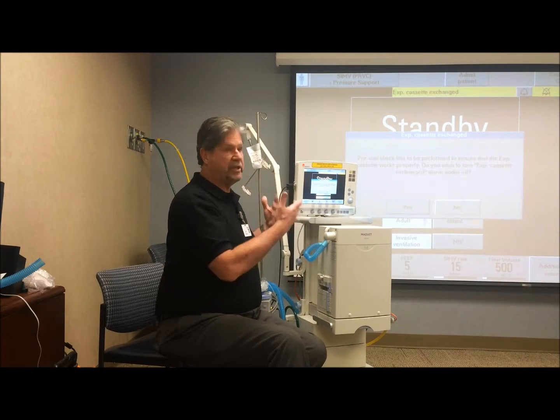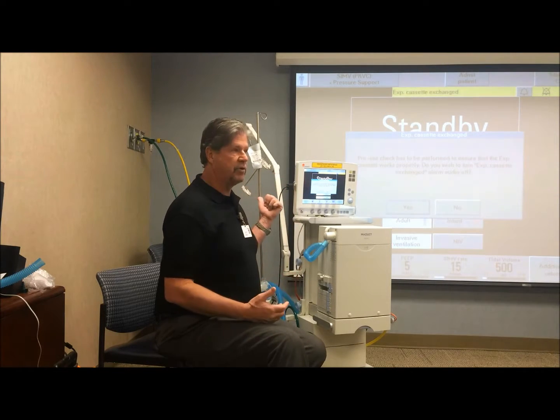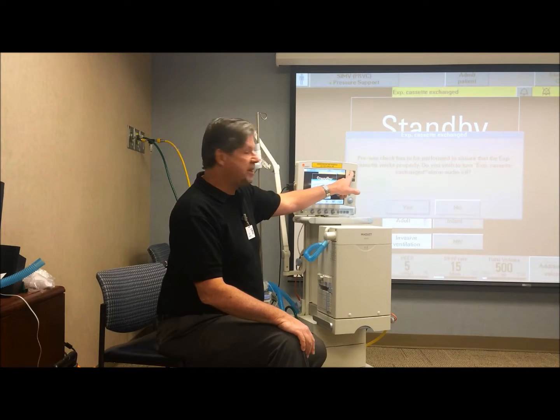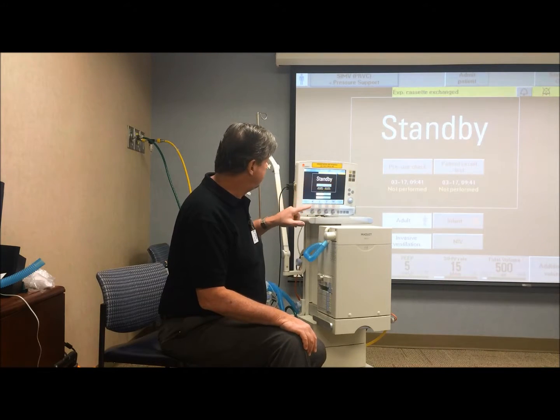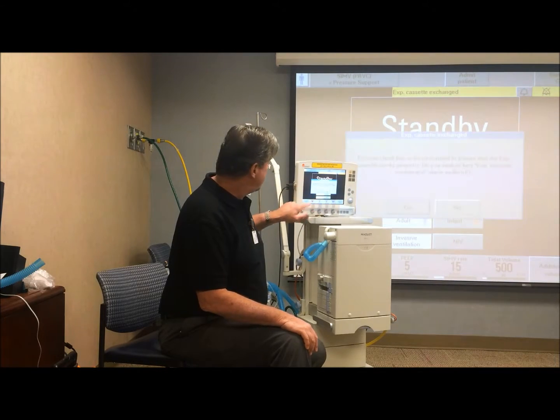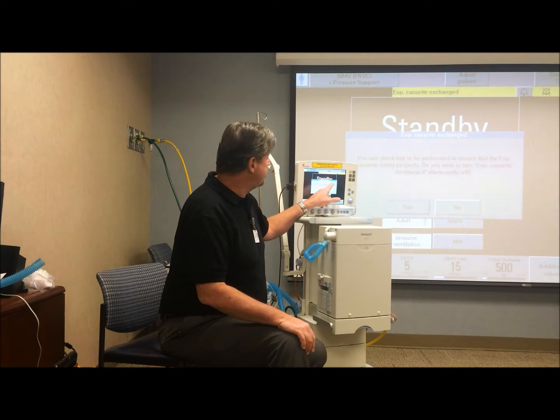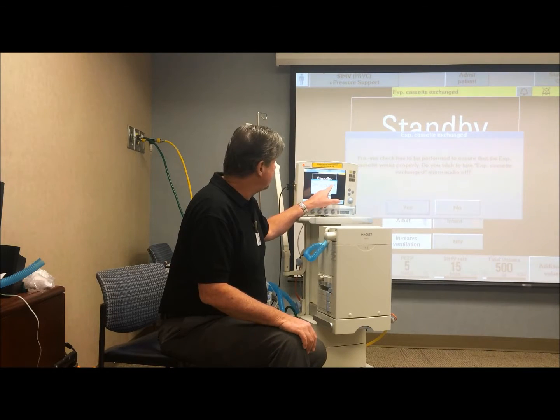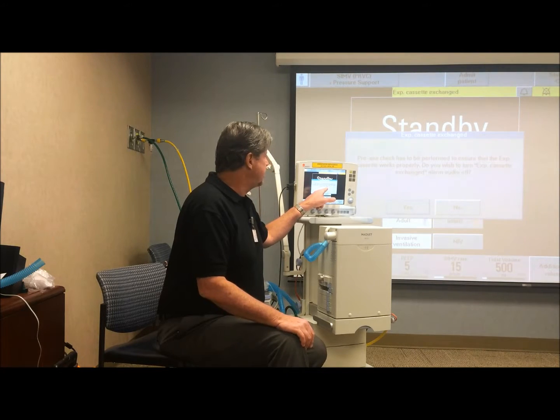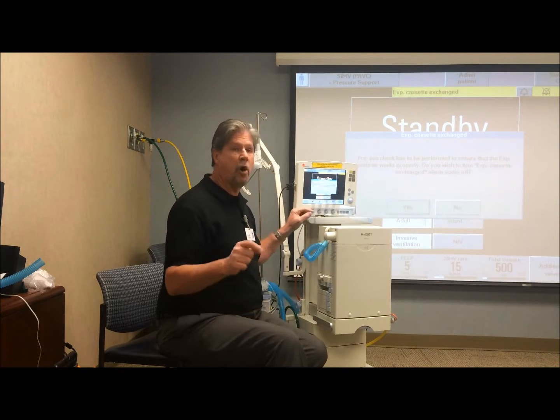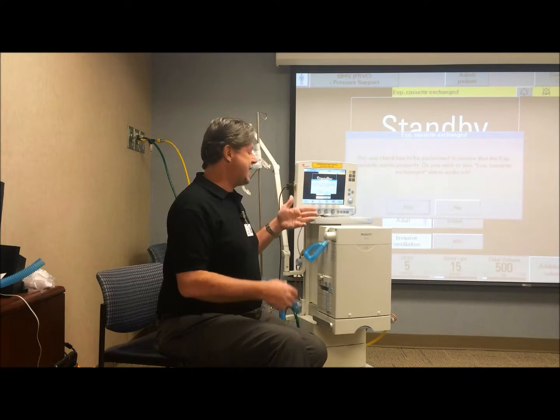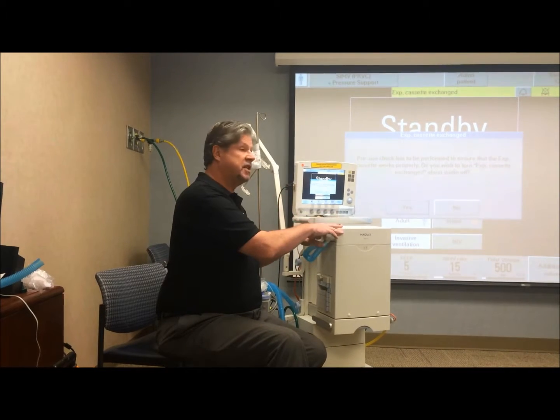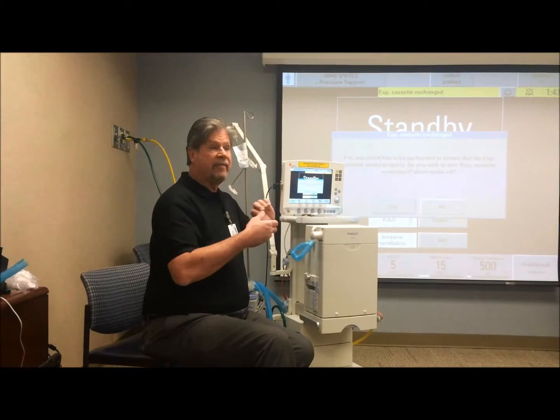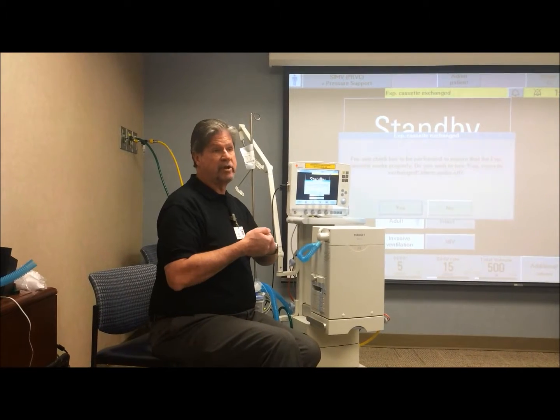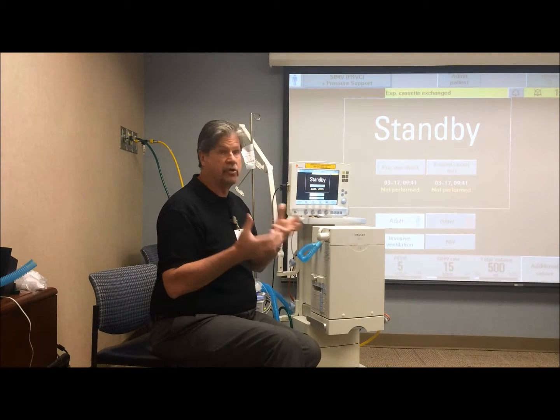Now, if you're in a situation like we are now, where we only have O2, when I hit the silence button, it tells me that a pre-use check should be performed or has to be performed to ensure that the expiratory cassette works properly. Do you wish to turn expiratory cassette exchanged alarm audio off? So what it's saying is that assuming that the cassette is working fine, the ventilator wants to shake hands with that particular cassette just to make sure that it's working all right.